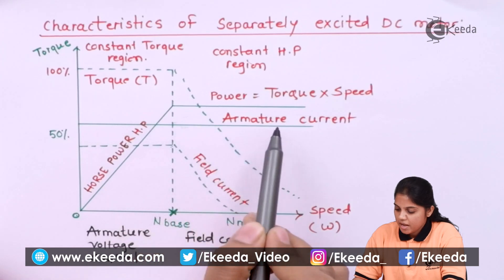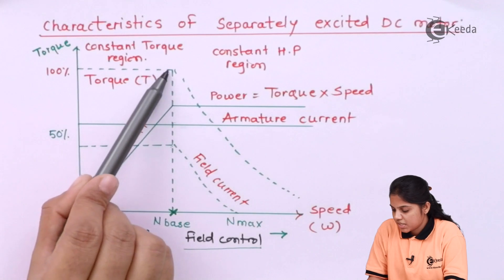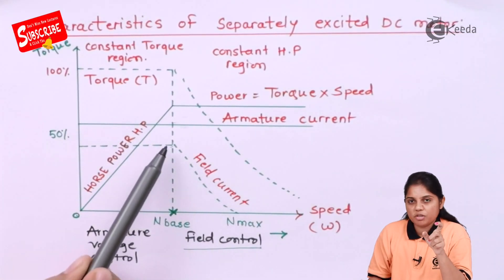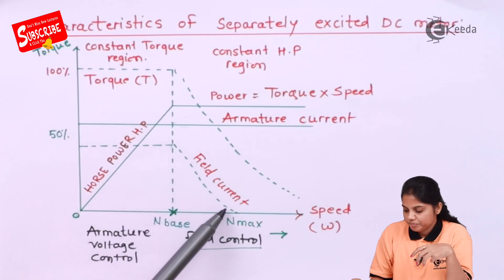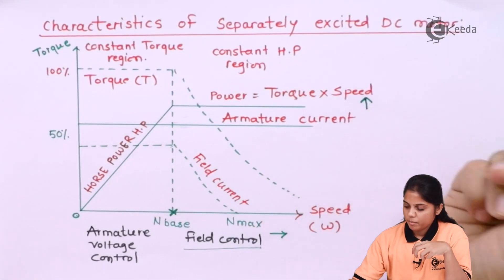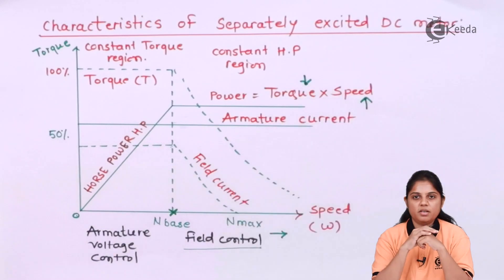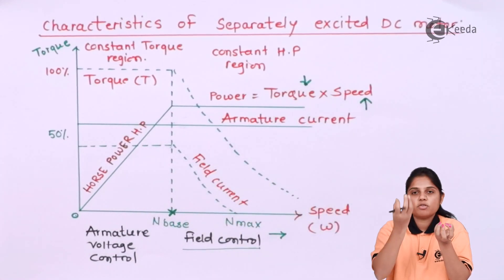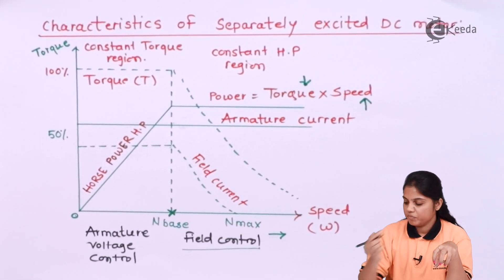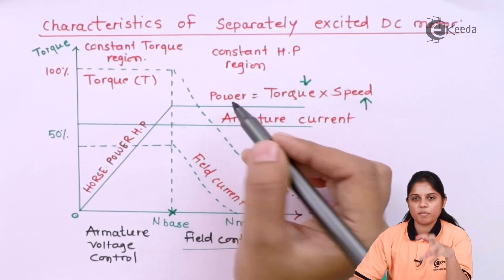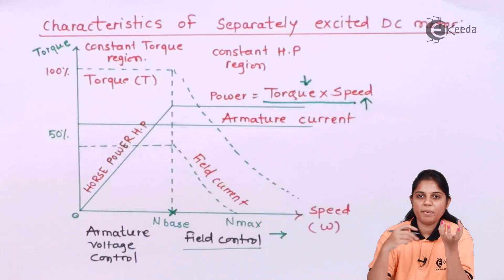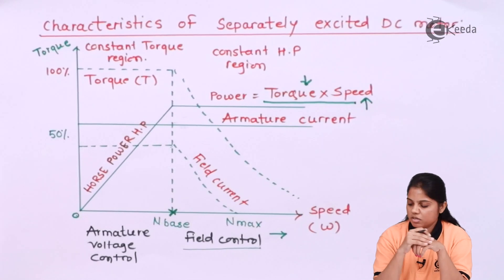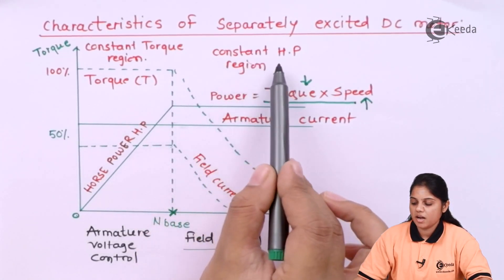As the field current decreases, the speed increases — the x-axis represents speed. At the same time, torque is also decreasing. With armature voltage fixed and field current decreasing, speed increases but torque decreases. Because of this, power remains constant: when torque decreases, speed increases, maintaining balance. Power equals torque multiplied by speed — if one parameter increases while the other decreases, the product remains constant.